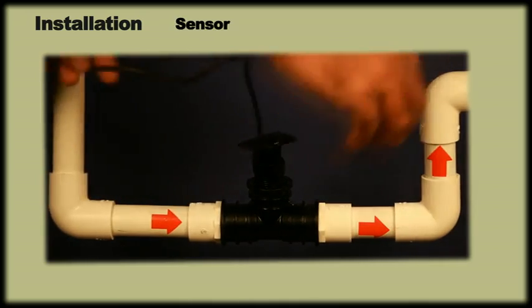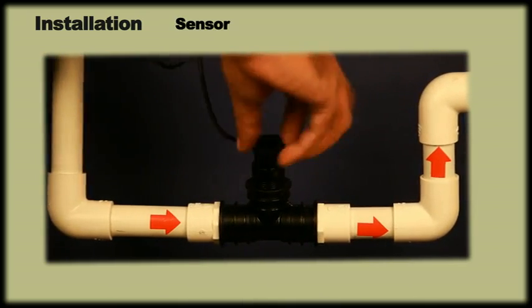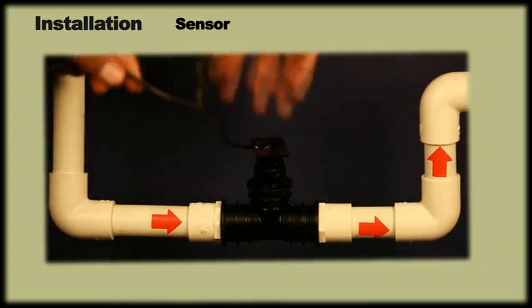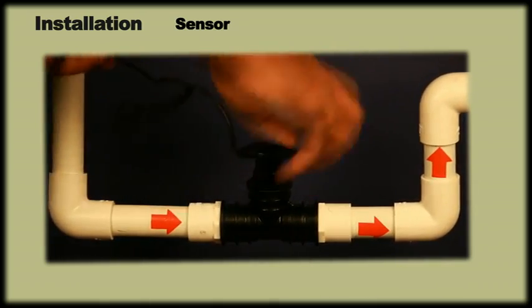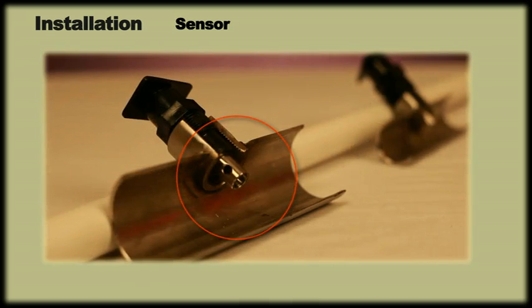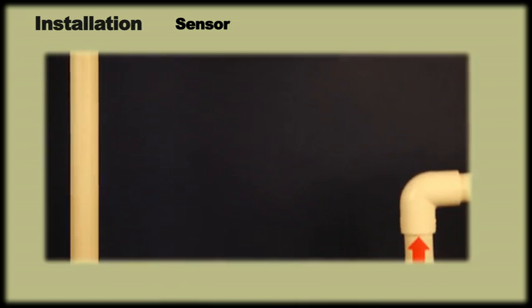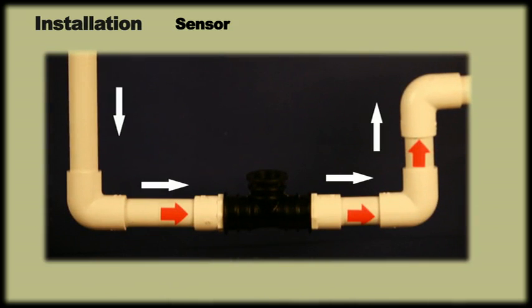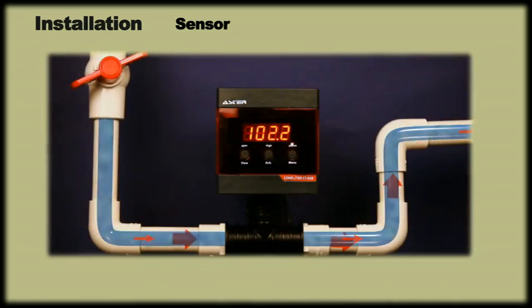Sensor Installation. When the sensor is installed directly into a pipeline without a standard sensor holder, please ensure that the electrode is completely dipped into water. It is very important to loop the outlet tubing or piping in U shape such that the sensor fitting always remains filled with water.